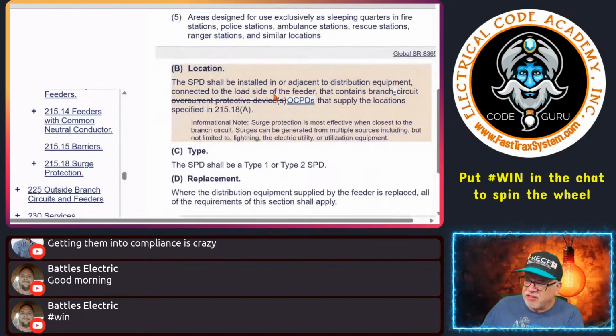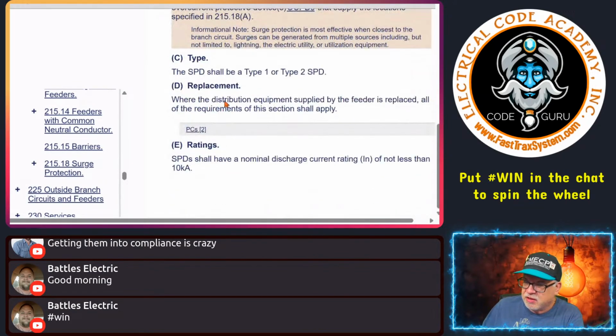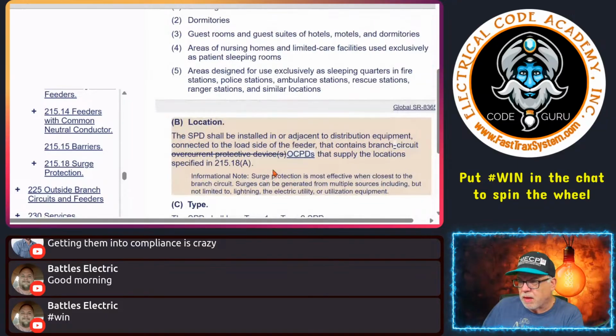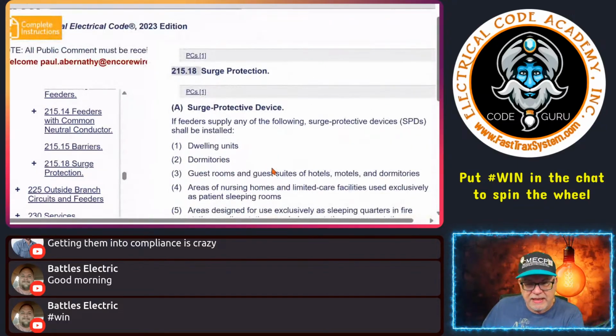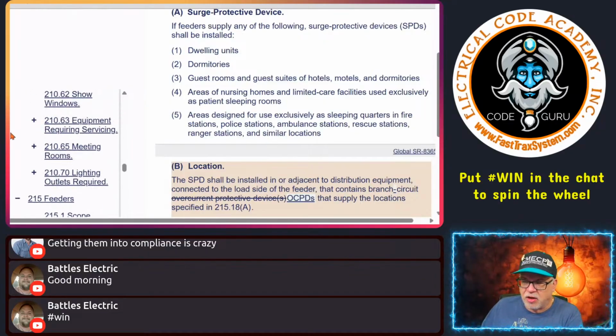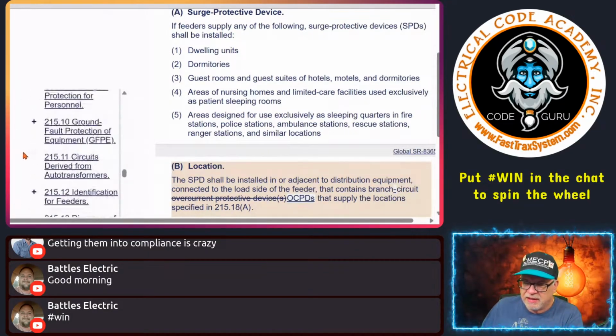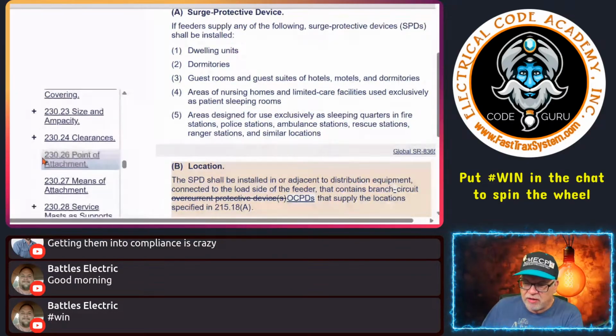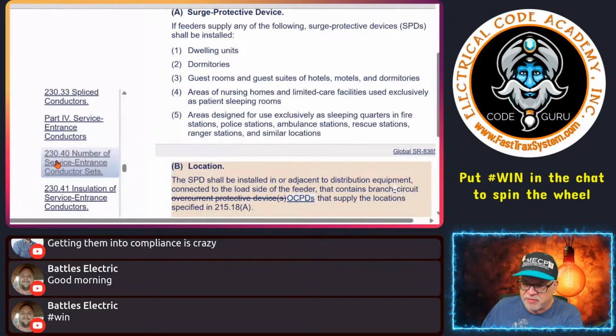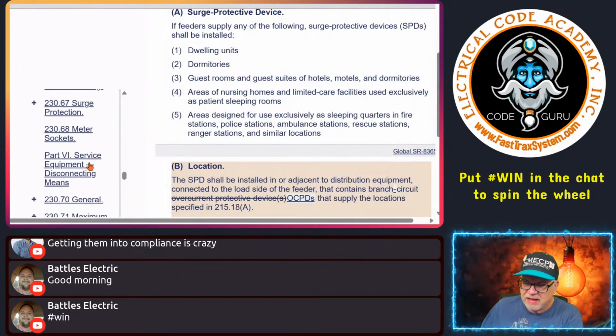Now, one of the changes is down here in the location. It says the SPD shall be installed in or adjacent to distribution equipment connected to the load side of the feeder. So that's in the feeder panel that contains branch circuits, overcurrent protective devices that supply the location specified in 215.18(A). Of course, this was heavily debated during the event, but at the end of the day, it went back to the way the code was. Now let's go back and look at the other one and see what happened there. That was 230, what I think is the main one, by the way, regardless of whether you put it at the service or at a remote panel, because you have an exception for that. But let's go back and see what it says in surge protection.